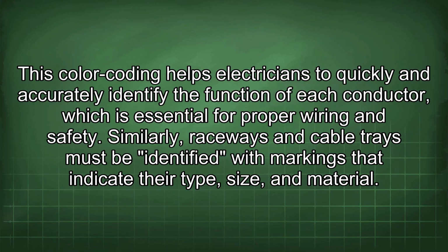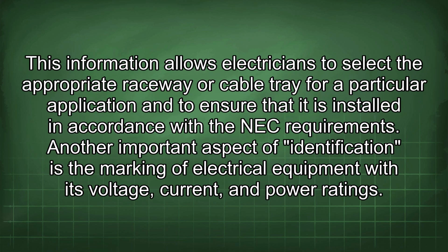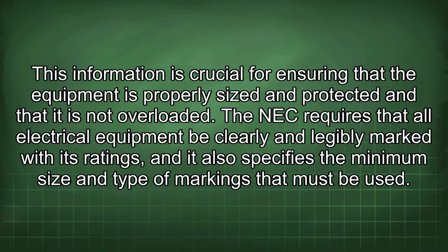Similarly, raceways and cable trays must be identified with markings that indicate their type, size, and material. This information allows electricians to select the appropriate raceway or cable tray for a particular application and to ensure that it is installed in accordance with the NEC requirements. Another important aspect of identification is the marking of electrical equipment with its voltage, current, and power ratings. This information is crucial for ensuring that the equipment is properly sized and protected and that it is not overloaded. The NEC requires that all electrical equipment be clearly and legibly marked with its ratings, and it also specifies the minimum size and type of markings that must be used.